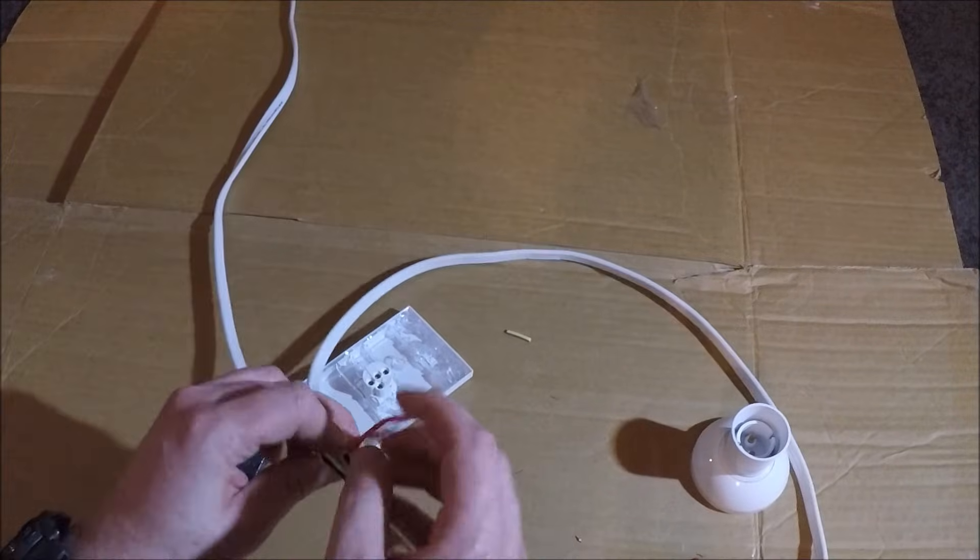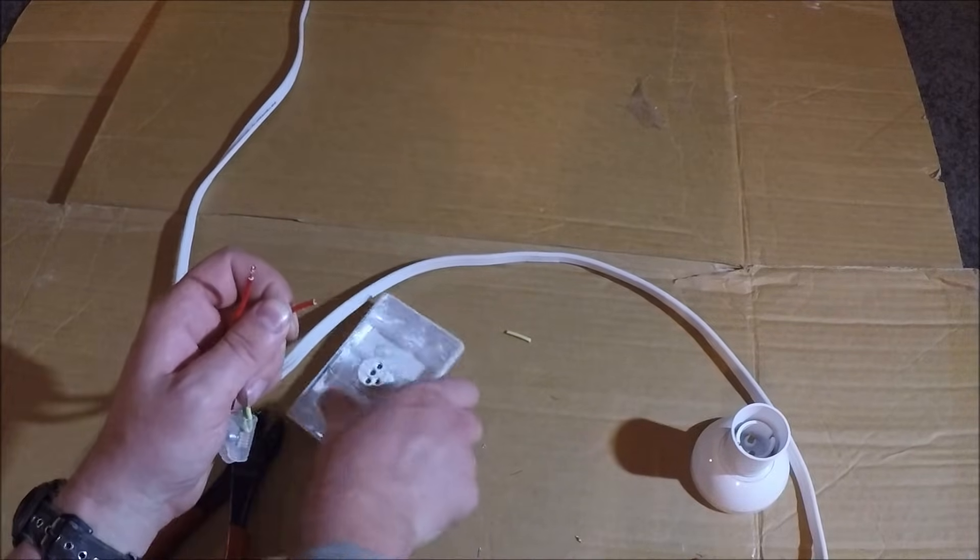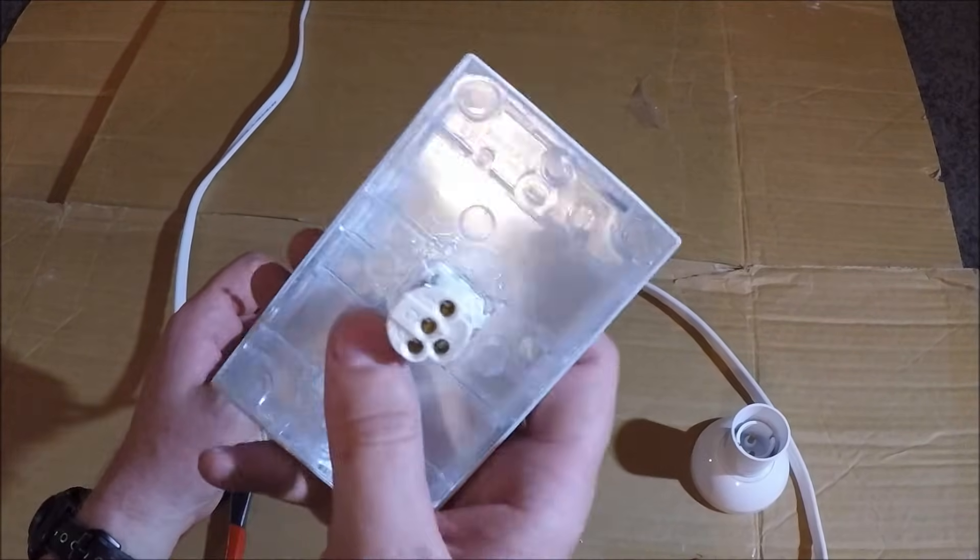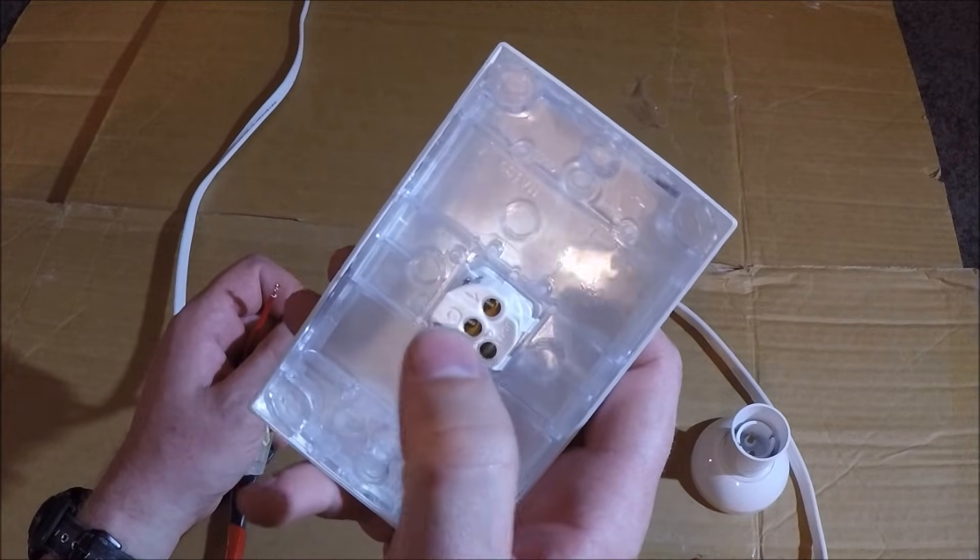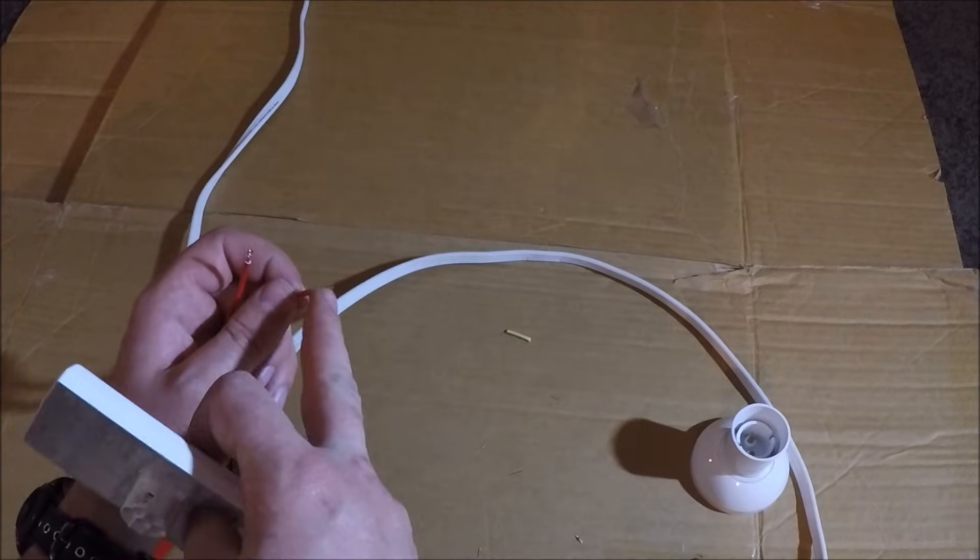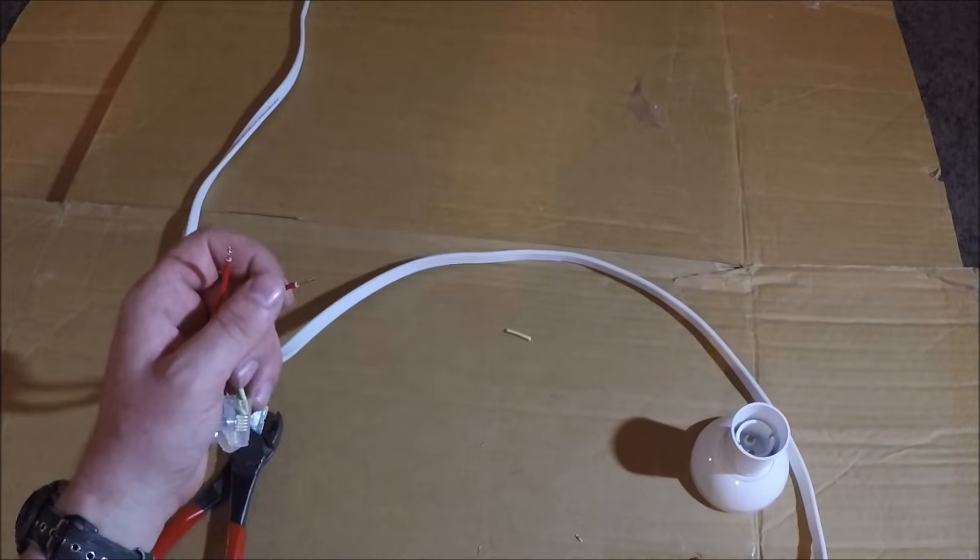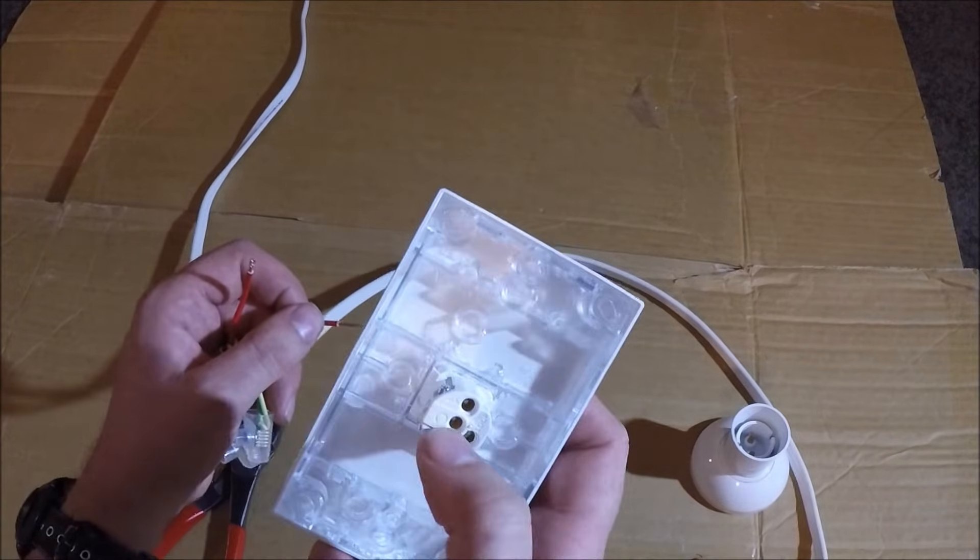So the next part is you've got your two cores here. This one here is from the switchboard. If you look on the back of the switch you'll have a one, a two and a C and a loop terminal. Now this one here as I said was from the switchboard so this one here we want to put into the C terminal in the middle here.